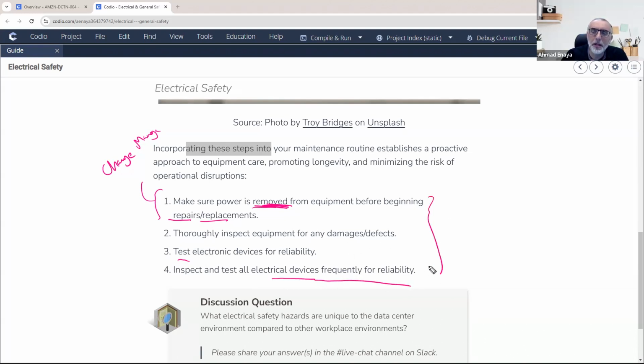One way to inspect electrical devices is using a heat scanner, because any failure or fault typically generates excessive heat in that area, so you know something is wrong. A faulty or high-resistance cable will show a lot of heat around it, so heat is a good, easy way to identify electrical failures using a heat scanner, which you should do regularly.